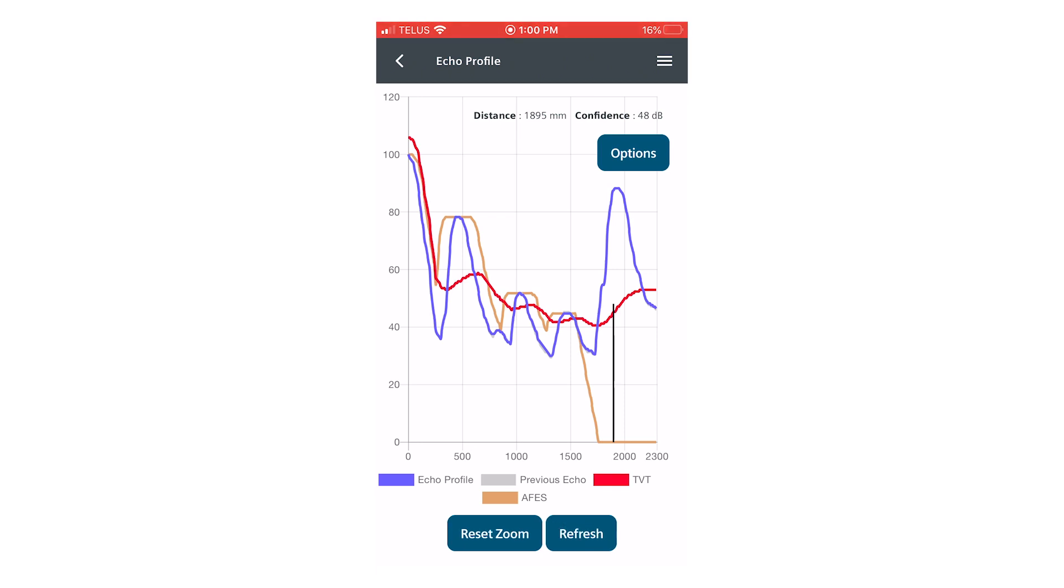You can see clearly the brown auto false echo suppression curve has now been drawn around the false echoes and those three echoes will never be selected in the future.